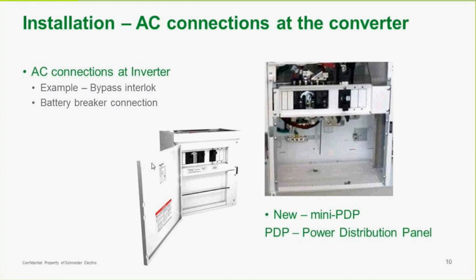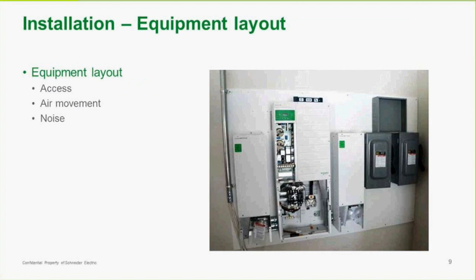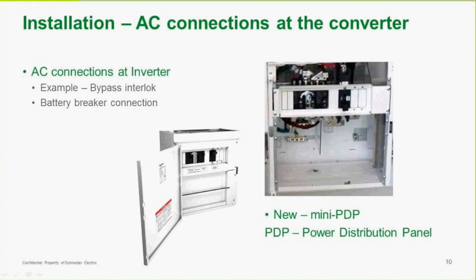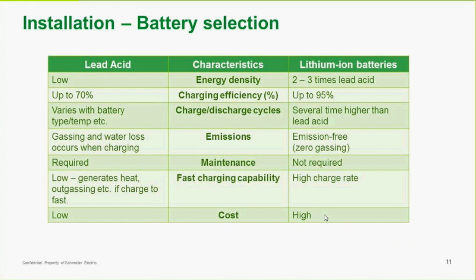There's also an installation power distribution panel that can be installed right underneath the XW Plus. This has got some AC breakers in it as well as a DC breaker, and it really simplifies installation for single unit installations like you see here. So this is that actual box, and it's called a mini PDP.